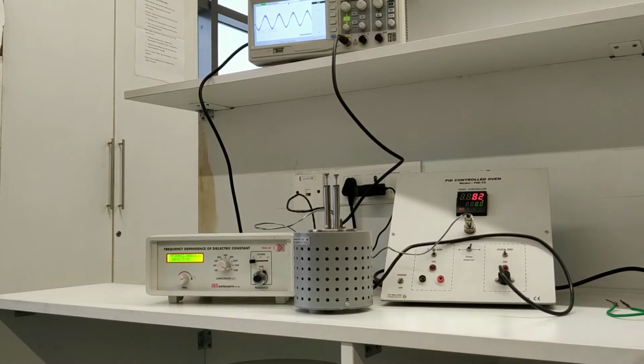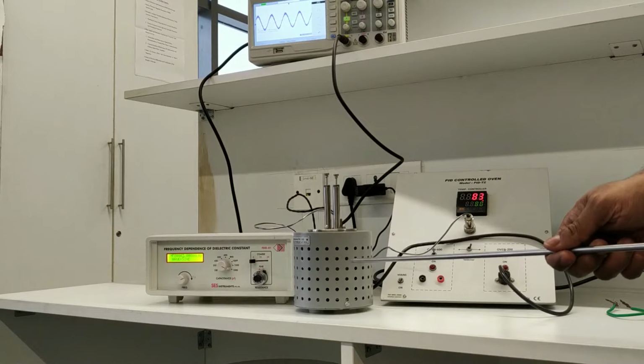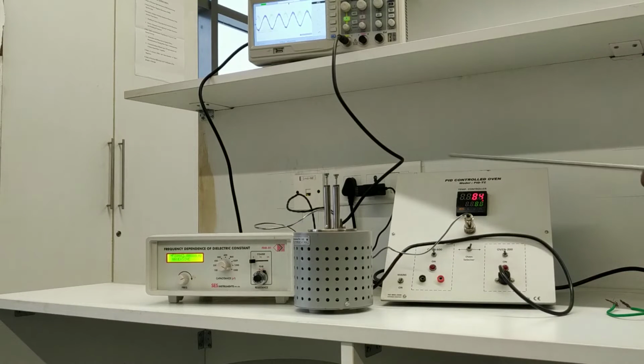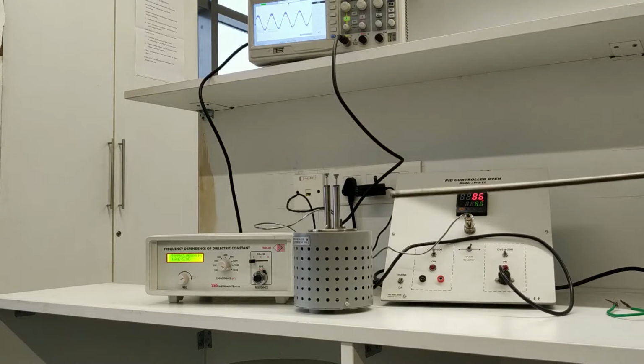Whenever you do any kind of experiment using temperature controllers, the basic idea is that there is a current supply that goes to the furnace, which by joule heating creates heat and creates the higher temperature, right? Once you reach 80, it will always overshoot 80. See, now it's 85. This is the actual temperature. The red one is the actual temperature, the green one is the set temperature. What the controller does is it tries to turn on and turn off the current to keep your temperature round about this value. Okay.